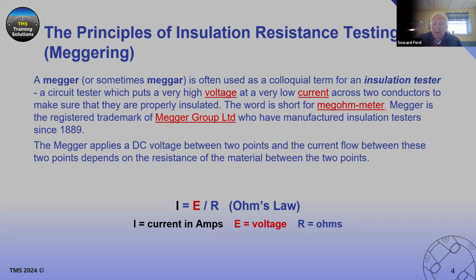Megger is the registered trademark of Megger Group Limited, who have manufactured insulation testers since 1889, located in the UK. The Megger applies a DC voltage between two points, and the current flow between those two points depends on the resistance of the material between them. So that's what we're measuring, the resistance between the two points.